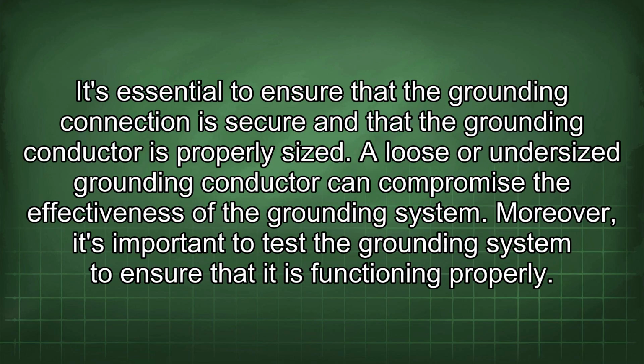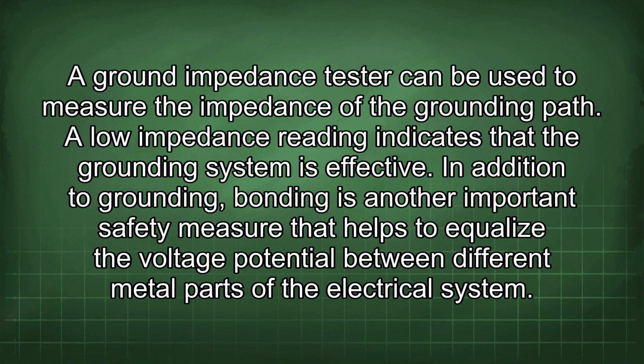It's essential to ensure that the grounding connection is secure and that the grounding conductor is properly sized. A loose or undersized grounding conductor can compromise the effectiveness of the grounding system. Moreover, it's important to test the grounding system to ensure that it is functioning properly. A ground impedance tester can be used to measure the impedance of the grounding path. A low impedance reading indicates that the grounding system is effective.